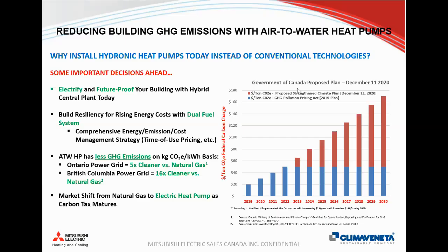Whenever I go to a job site and go into a mechanical room and I see a bunch of big boilers, the first thing I'm thinking of is, okay, how are we going to get power here to run the heat pumps to offset all this natural gas? So there's a lot of good reasons why you can still look at building resiliency into your systems by having a dual fuel system. With air to water heat pump technology, there's limitations to how cold you can run the equipment, -15, -20. It doesn't really matter because in most places in Canada, our design temperature is below -20 anyway. So you need an auxiliary heat source in the building anyway.